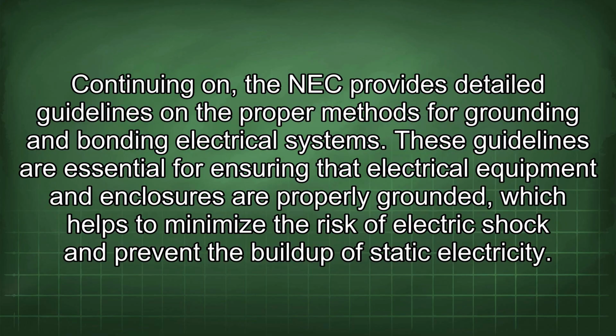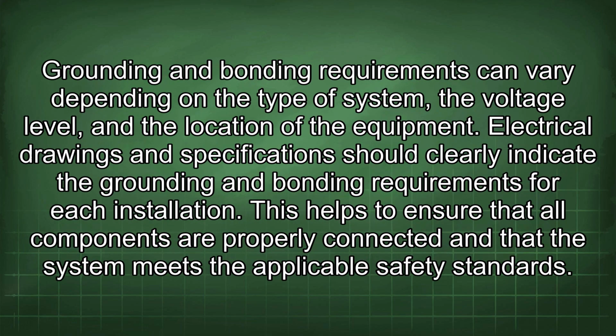Continuing on, the NEC provides detailed guidelines on the proper methods for grounding and bonding electrical systems. These guidelines are essential for ensuring that electrical equipment and enclosures are properly grounded, which helps to minimize the risk of electric shock and prevent the buildup of static electricity. Grounding and bonding requirements can vary depending on the type of system, the voltage level, and the location of the equipment. Electrical drawings and specifications should clearly indicate the grounding and bonding requirements for each installation. This helps to ensure that all components are properly connected and that the system meets the applicable safety standards.